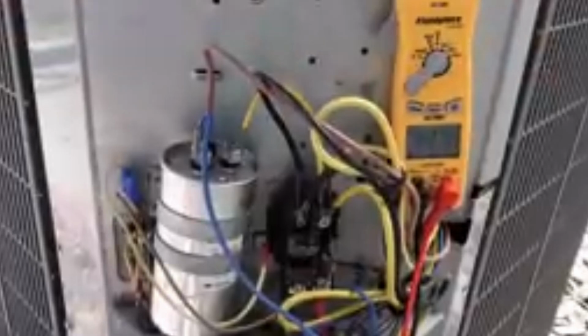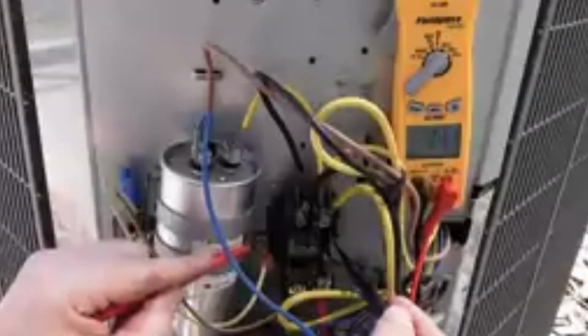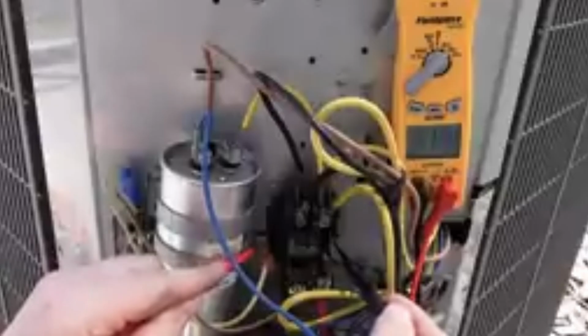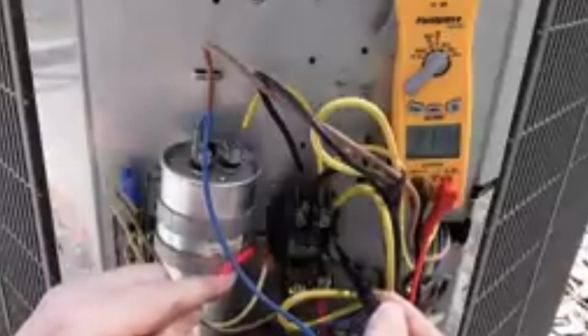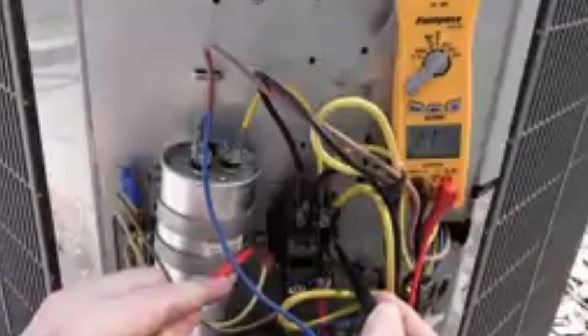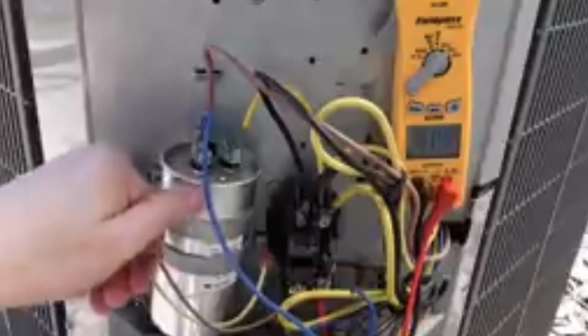Let's go ahead and just show this measurement. Whenever you have an energized load, you should read nearly the full applied voltage across it. And as you can see, we have 24.7 volts across this contactor coil, which is exactly what we would expect. This is our run capacitor.